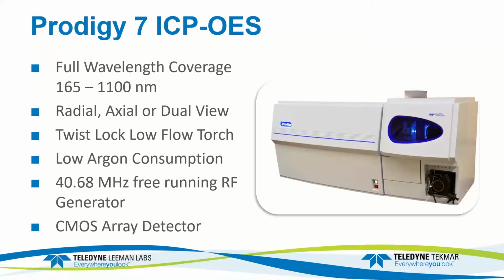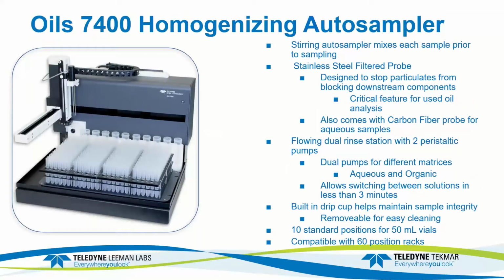The main difference is the optical system. The Oils 7400 Homogenizing Auto sampler. This auto sampler has the ability to mix samples before they are analyzed, particularly for oils. That's advantageous because if they sit for a long time, you can get some separation, particularly when the oils are really heavy and you have a really long analysis time, and it may be hours before a particular sample is analyzed. So this auto sampler has a probe and a mixing paddle that can mix that sample up.